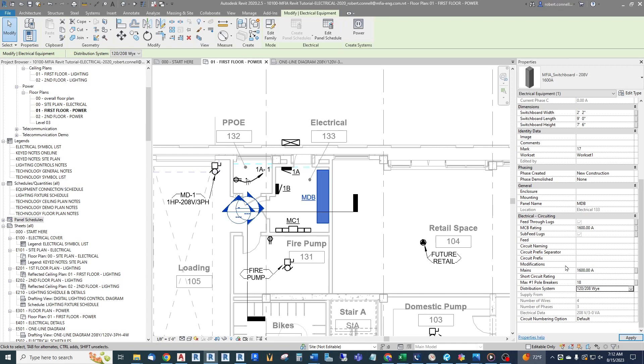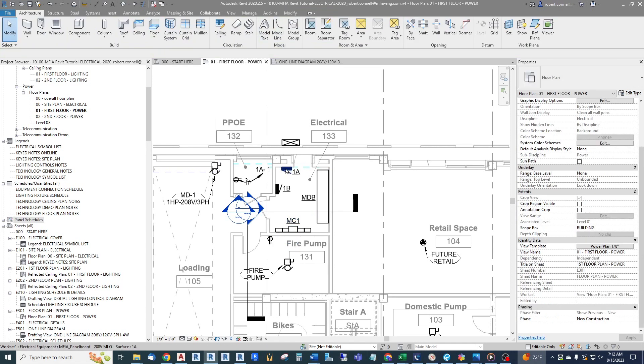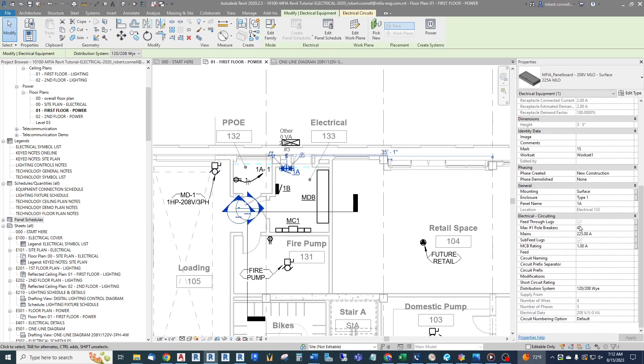We can do the same for the other equipment. Our meter center — the center piece of this lineup that we connect — is called MC1 and is set up for 120/208. Panel 1A has some ratings and can have 42 breakers, also 120/208. Same for panel 1B — 120/208. All of these look compatible as far as voltage and phase. If they were mismatched, Revit would not let us connect them and we would have to adjust accordingly.